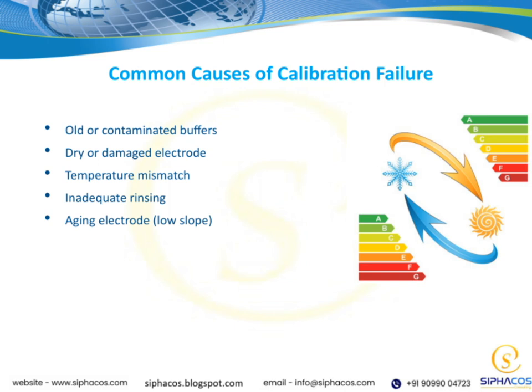Inadequate rinsing between measurements can also introduce errors, so it's important to rinse thoroughly to remove any residual substances. Lastly, an aging electrode with a low slope indicates that the electrode is losing its responsiveness over time, which means it may need to be replaced to maintain calibration accuracy. These factors all tie into our overall goal of ensuring precise and reliable measurements, so paying attention to them will help maintain the integrity of your calibration process.